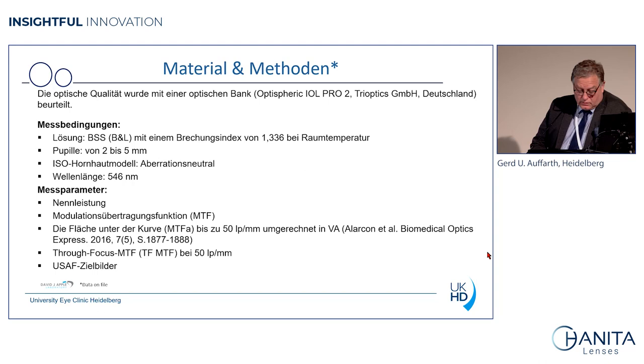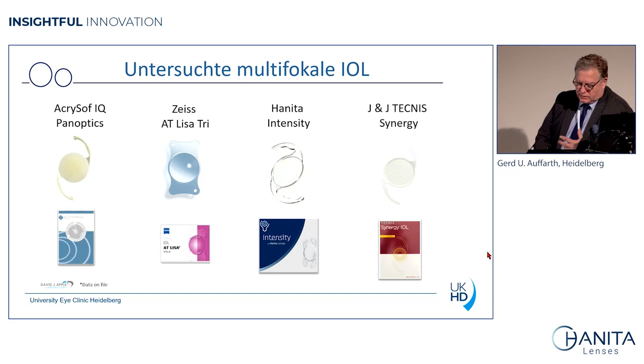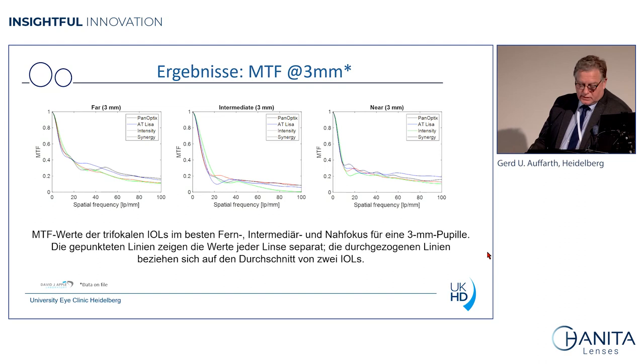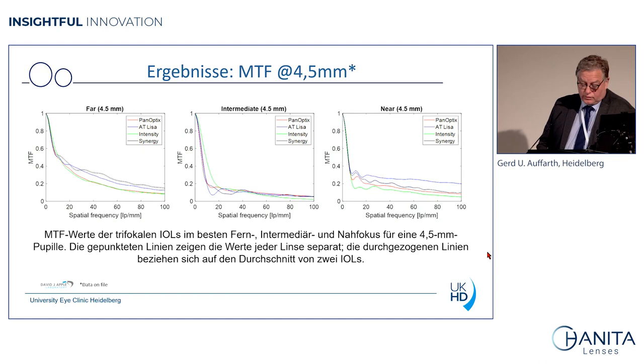We compared the Intensity with the Panoptix, the AT LISA tri, and the Tecnis Synergy. The Synergy is a mixture of a bifocal and an EDOF lens, while the others are trifocal — the Panoptix even pentafocal. The idea was to look for non-inferiority. Looking at the MTF curves, which give an idea about image quality at different spatial frequencies, there is essentially no difference at far, intermediate, and near at a 3 mm pupil. At a 4.5 mm pupil the outcome is the same as well.